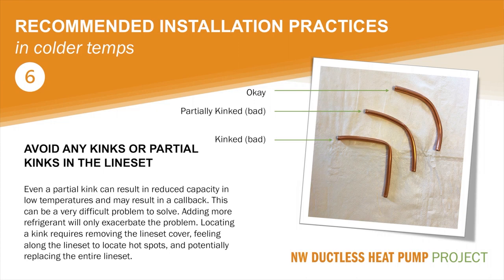Partially kinked line sets are a surprisingly common problem, especially with larger capacity indoor units which have 1/2 inch or 5/8 inch line sets. These tubes are prone to partial kinking.